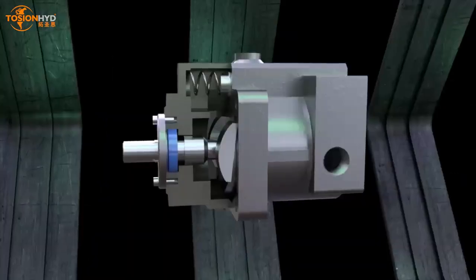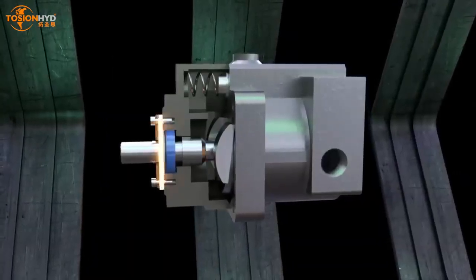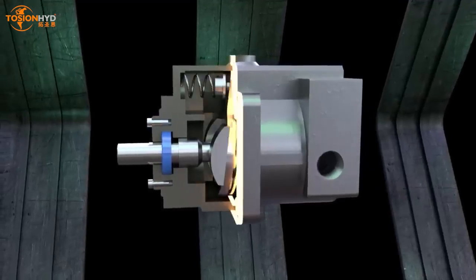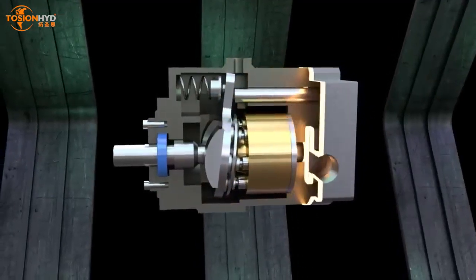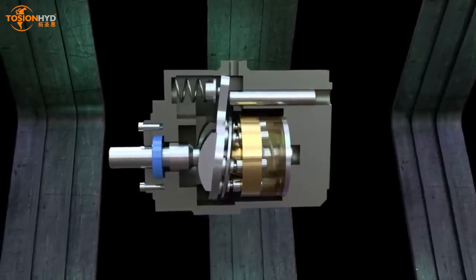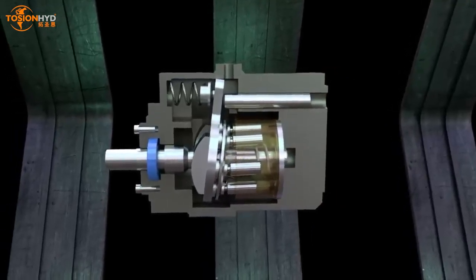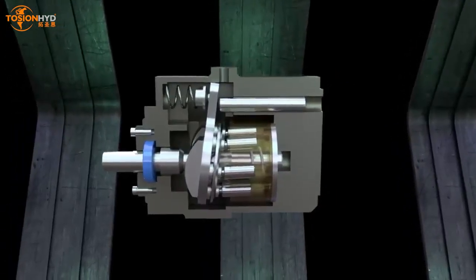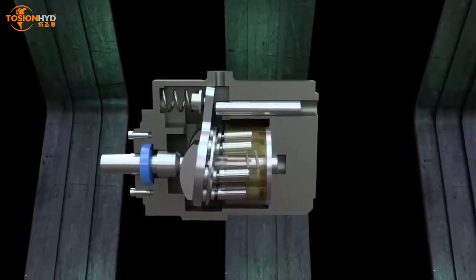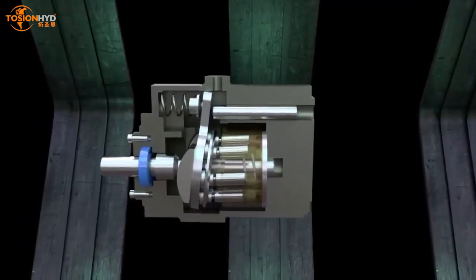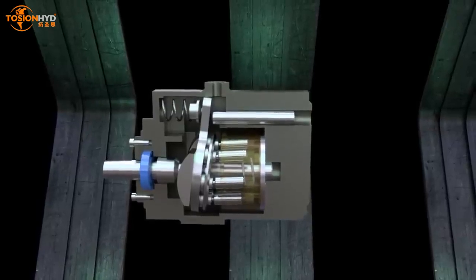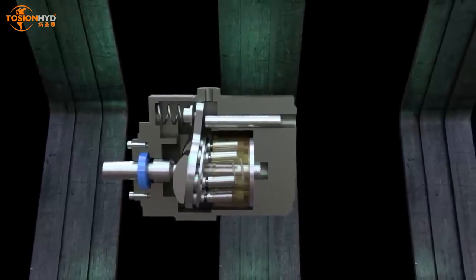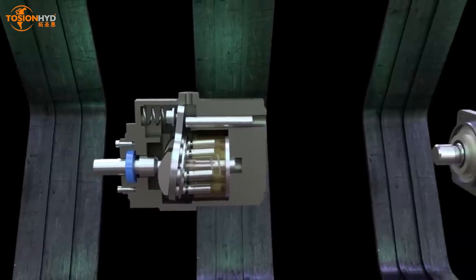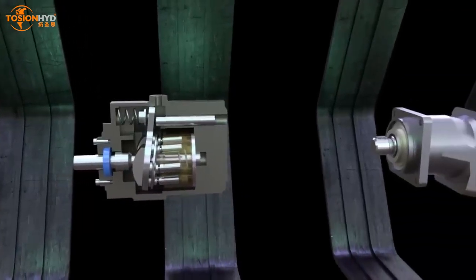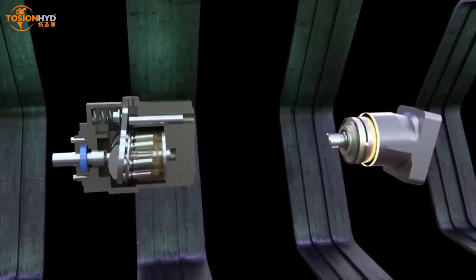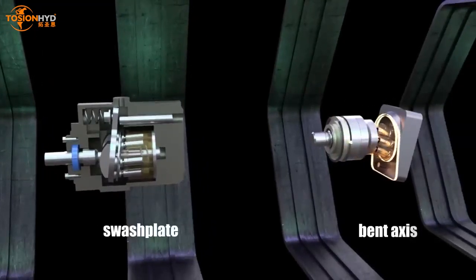In axial piston pumps, the pistons are parallel to the axis of rotation of the shaft, or slightly inclined at an angle of not more than 45 degrees. To pump fluid, the pistons in the pump must move forward while the drive shaft rotates. Converting the rotational motion of the input shaft into the translational motion of the pistons is possible due to the inclined position of the bent axis, or the swash plate on which they rest. In the first case, the device is called a bent axis pump. In the second case, it is a swash plate pump.